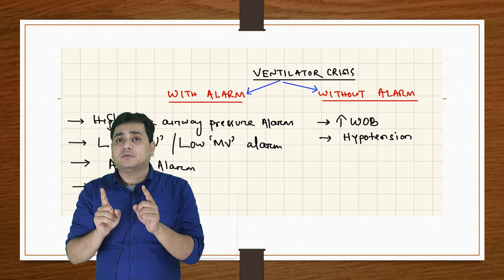Before discussing the peak airway pressure alarm, we will discuss the airway. If we consider the human respiratory system, it is comprised of 2 things, one cylindrical structure and one globular structure. From physics class, if you can recall, in an ohmic conductor, a cylindrical wire-like structure, the potential difference between the 2 ends is directly proportional to the current flowing through it times the resistance. The same will apply here. The pressure difference between the beginning of the airway and the end of the airway, called the trans-airway pressure, will be proportional to the air flowing through it times the resistance. Now in a cylindrical structure, when something flows, it has to overcome a resistance because it cannot expand. But in a globular structure, it will expand, so all the resistance will be dissipated.